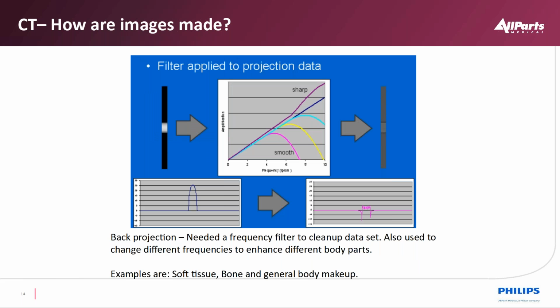So this is an example of what we would be doing. So on the left, we have an example of maybe a rod that we scanned. We run it through an algorithm. Now we can take that algorithm and have it smooth. So smooth would be low changes or small changes in CT number in the sample. Sharp would be higher changes like bone, or somewhere they would call it detailed in certain manufacturers. So we can pick those algorithms.